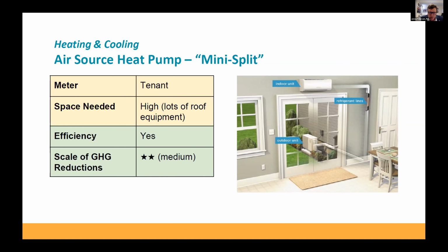So if you have a 1-bedroom or 2-bedroom, this ductless unit isn't a great solution. In that case, you can still have a single indoor vertical fan coil unit that's ducted to provide supply air to the living space and first bedroom, then ducted across to pick up a second bedroom, returning air through transfer grills. There are other indoor unit styles too, with air source heat pumps, both 1-to-1 and VRF, which we'll talk about. So there's a lot of flexibility with this type of equipment in general.